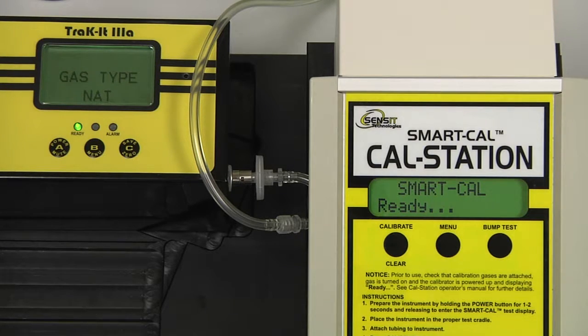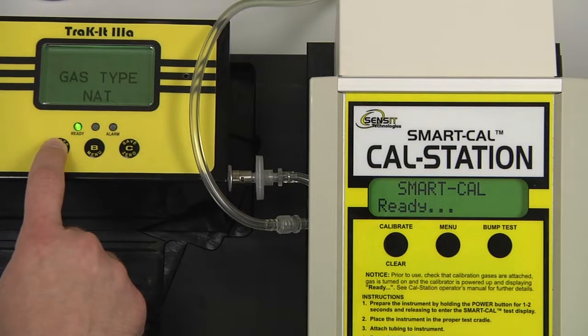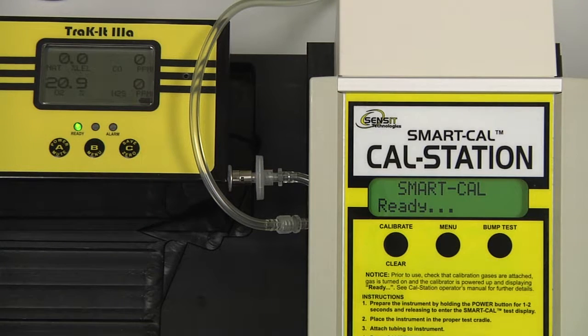If we wanted to calibrate for propane, we would press and release the C button to display PRO in the bottom right, and then press and release the A button until you return to the working display. In this case, we're going to calibrate for methane, so we can press and release the B button. We go back to that, and press and release the A button until we get back to the working display. In the upper left, we'll have an indication NAT for natural gas or methane for the selected gas type. Allow the instrument to warm up for an additional 5 minutes before calibrating.